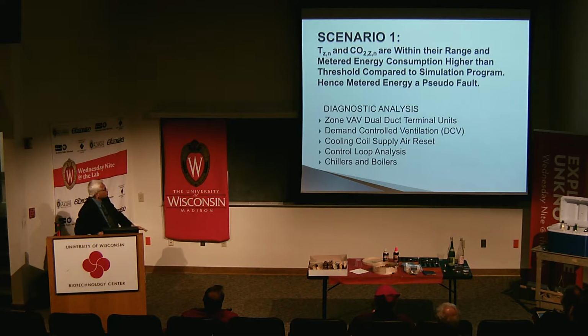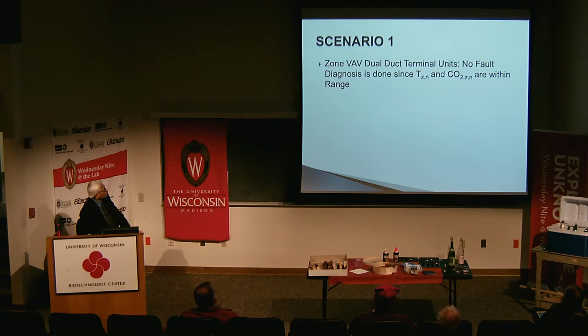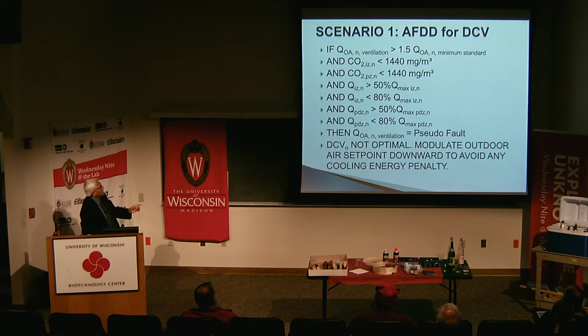So first thing I'm looking at is VAV system with dual duct terminal units, demand control ventilation. I will explain what it is. Cooling coil supply reset, I already talked about it. I will go through that. Control loop analysis and chillers and boilers. Now the first scenario, as I said, both temperature and CO2 for all zones, perimeter zones, interior zones are within the range. Now I am looking at this AFDD for demand control ventilation. Demand control ventilation is nothing but you allow enough ventilation to come in to satisfy the CO2 requirement, that it has to stay within a certain parts per million, like 1,000 or 1,200.